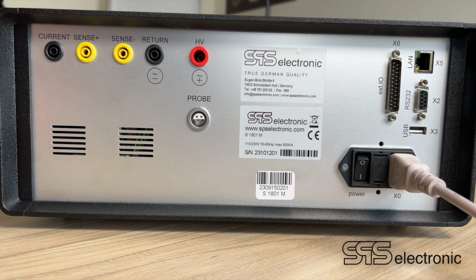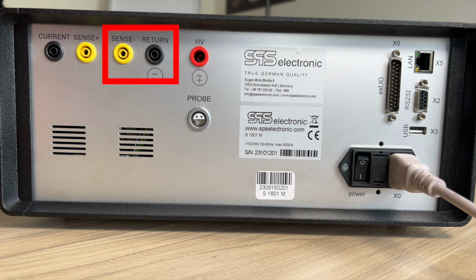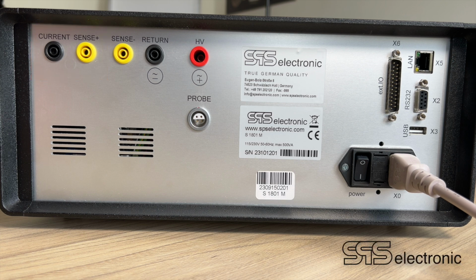Because we are using ground bond test for a four-wire measurement, we always need 4 cables. The first two are sense minus and return. The second two are current and sense plus. The sense minus and return will always be connected.